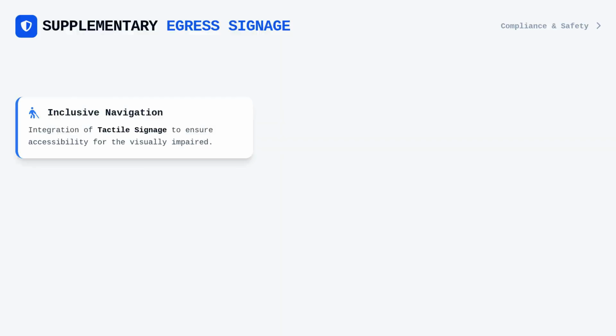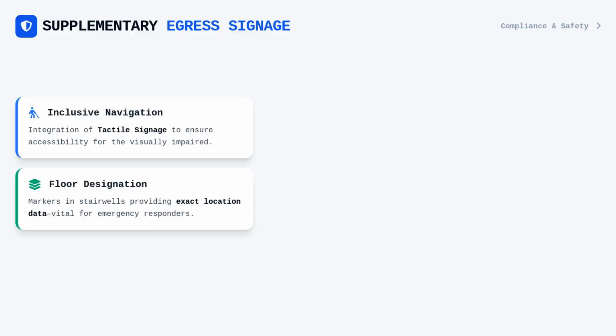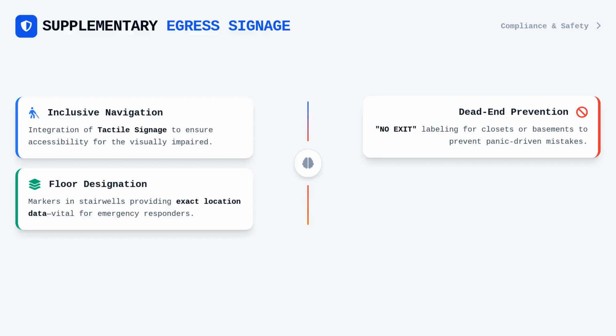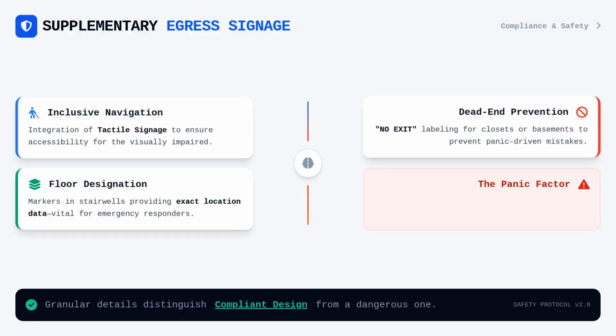In institutional or complex architectural settings, we occasionally require supplementary signage to avoid confusion for the occupants. This includes tactile signage for the visually impaired and specific floor designation markers within enclosed stairwells. A floor designation sign helps someone realize exactly where they are in the building, which provides critical information to responding fire department personnel. Conversely, we must also consider the placement of no exit signs on doors that might be mistaken for an exit during a panic situation. If a door leads to a basement, a closet, or an area that does not provide a safe route outside, code often mandates labeling it to prevent a dead-end mistake. These small, granular details are exactly what distinguishes a compliant egress design from a dangerous one, as the psychological aspect of panic often leads people to follow familiar architectural clues rather than logic.